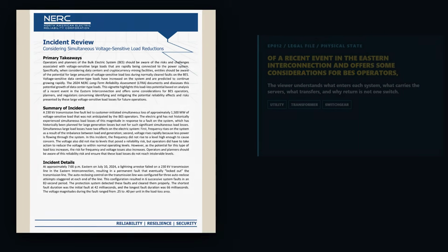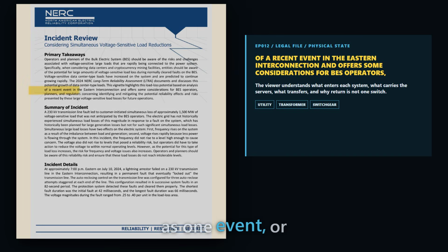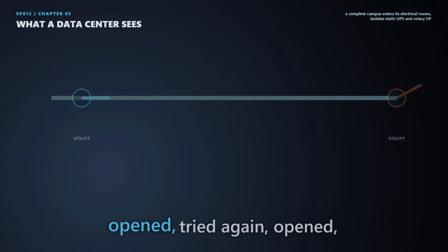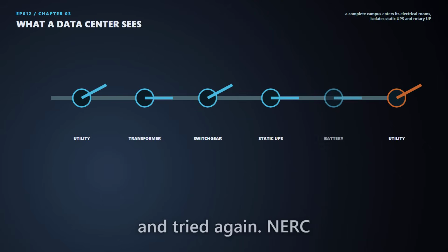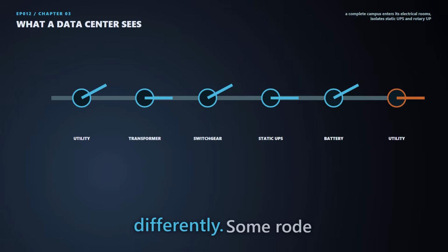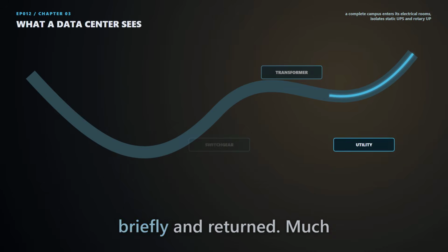Did the controller count a fault and the immediate reclose as one event or 2? In July, the first depression was not the whole story. The line opened, tried again, opened, and tried again. NERC found that facilities responded differently. Some rode through, some transferred briefly and returned.